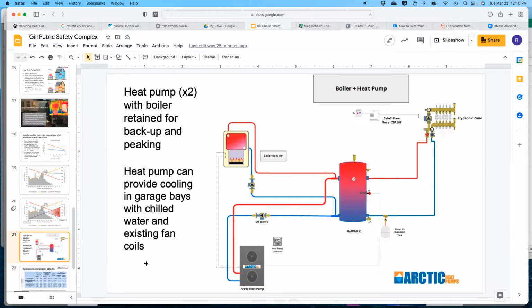I think I missed it, what was the domestic hot water for the building? It's very small, we didn't consider separating it. Right now I don't even remember, we looked at it, it was just inexpensive. I think it was electric resistance heating. If they did the system we're recommending, I would recommend eliminating or preheating the water for that electric resistance heater off of the buffer tank we're recommending.